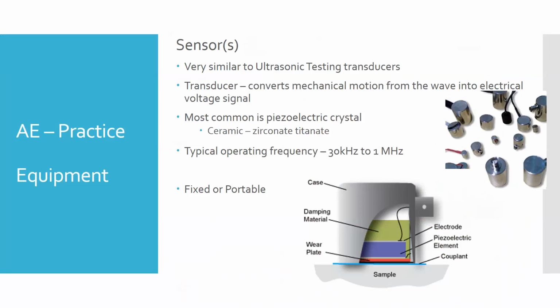Same thing, you want the energy coming in from the side of interest, in this case, the bottom. The top has damping material and other stuff to limit the amount of vibration coming in from not the correct direction. So our transducer converts that mechanical motion into an electrical signal that can then be analyzed by a computer and shown on a display.